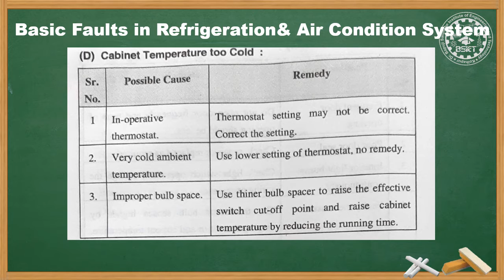Next is the cabinet temperature too cold. Possible causes are inoperative thermostat. Thermostat setting may not be correct. Set the thermostat to the proper setting. Very cold ambient temperature. Use a lower setting of thermostat. And improper bulb space. Use a thinner bulb spacer and raise the effective switch cutoff point.